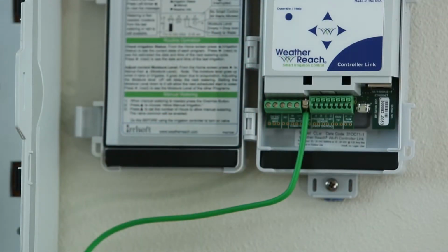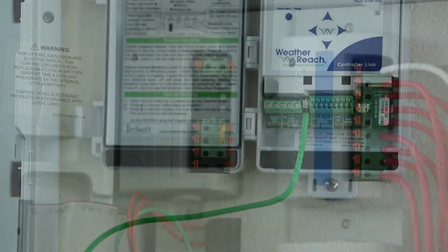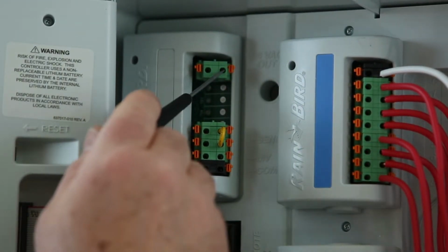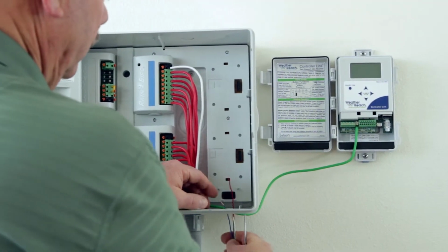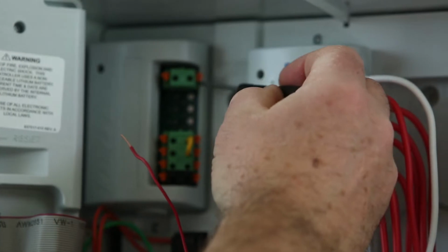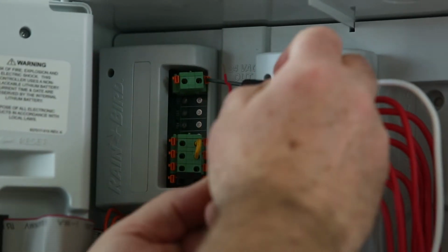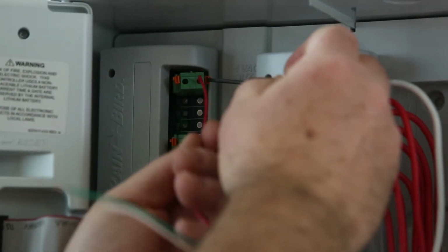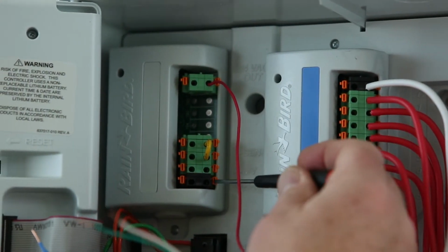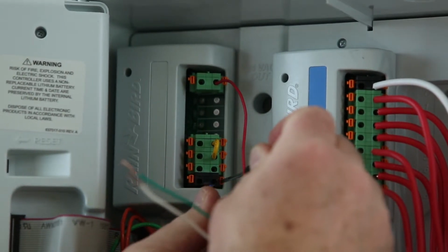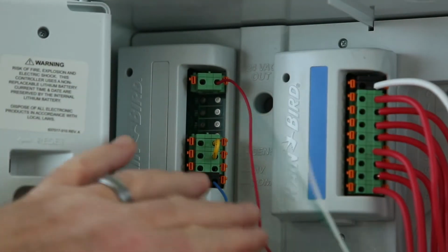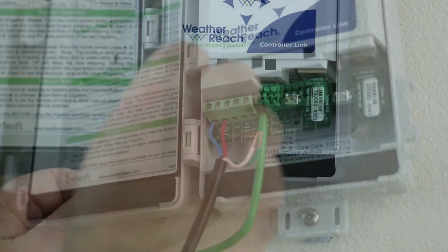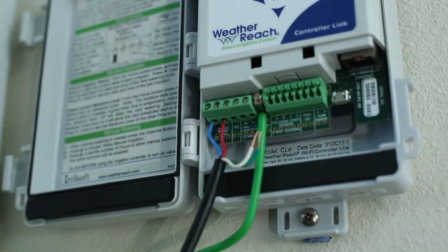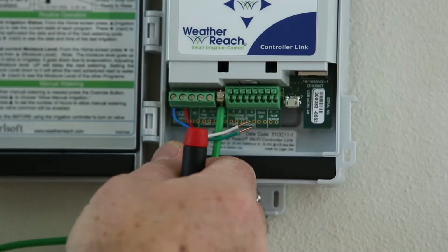Controller link needs power from the host controller. Locate the 24-volt power terminals in the controller. If you have any doubt, use a voltmeter to verify the power terminals. To make the power connection, choose 2 wires from one of the 4-strand cables. Connect the wires to the 24-volt power source in the host controller. Now connect the same wires to the 24 VAC power input terminals in the controller link. Make sure the connections are secure.